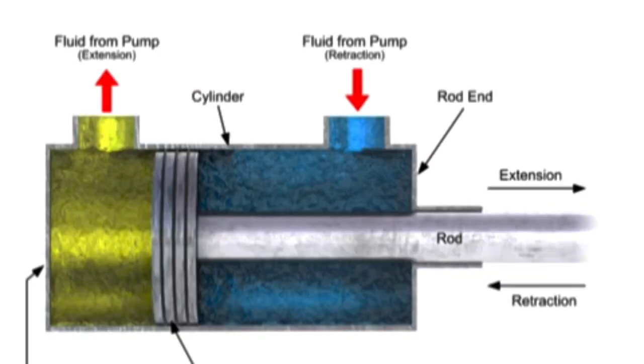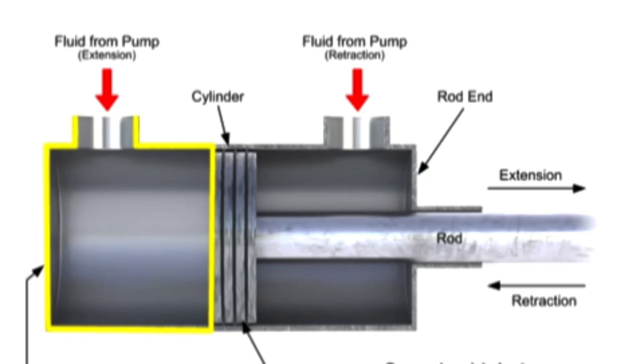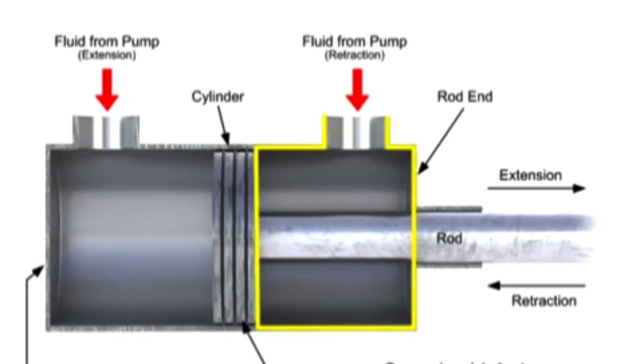The speed at which the piston extends and retracts is calculated using the volumetric flow rate, divided by the area for the incoming fluid. Since each side of the cylinder has a different working area, each side experiences a different speed.